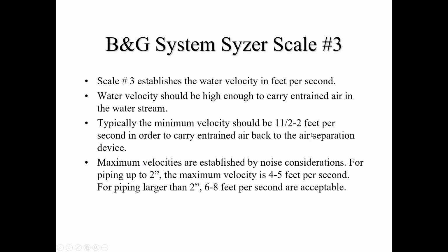Scale 3 establishes the water velocity in feet per second. It's the one and only time where the scales actually work together. Like I said, on scale 1, you figure out your flow rate based on BTUs and delta T. When you go down to scale 2, you're not working together. But in this one example, scales 2 and 3 work together. Whatever we find in 2, we don't move it. We just glance down and start looking at 3.